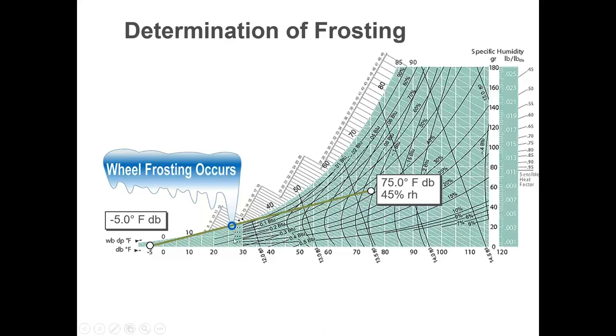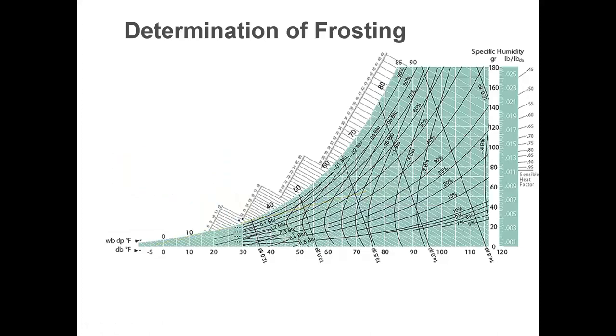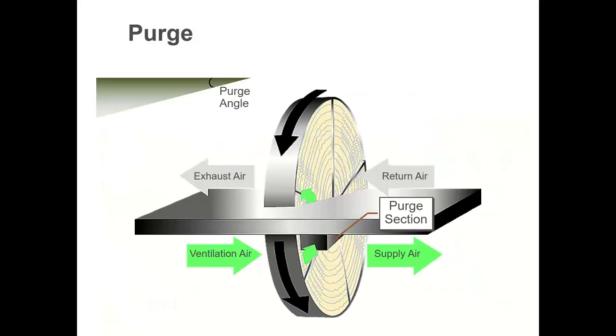So if I don't want that to be a problem, I have numerous different choices, but essentially my choices come down to, I either need to warm up this air, and let's say I warm it up 10 degrees, the outside incoming air from -5 to +5. And then if I redrew the line, it probably wouldn't hit the 100% saturation curve. So I either need to warm up the outside air or, believe it or not, warm up the exhaust air that's leaving. And that's actually the better way to do it. If I warm it up from 75 to like 85, and then redraw the line, I also will not hit the curve. Now it seems stupid to warm up the exhaust air that you're going to throw away. Like, why the hell would you do that, Ryan? If I have a better drawing on that, let's use this example. Why would you warm up this return air that's going to leave?